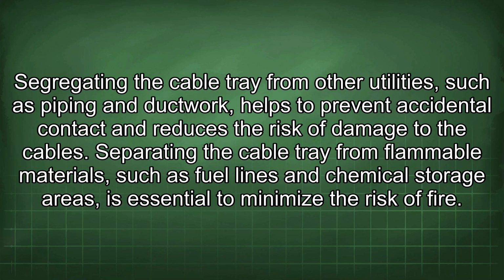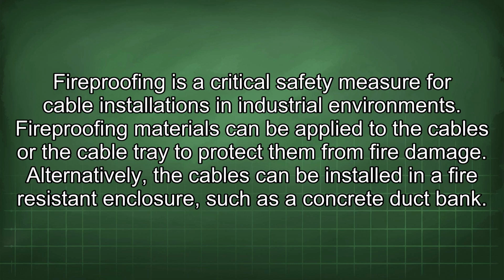Separating the cable tray from flammable materials such as fuel lines and chemical storage areas is essential to minimize the risk of fire. Fireproofing is a critical safety measure for cable installations in industrial environments. Fireproofing materials can be applied to the cables or the cable tray to protect them from fire damage. Alternatively, the cables can be installed in a fire-resistant enclosure, such as a concrete duct bank.